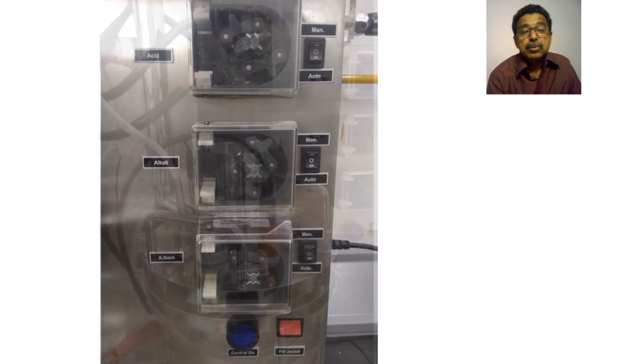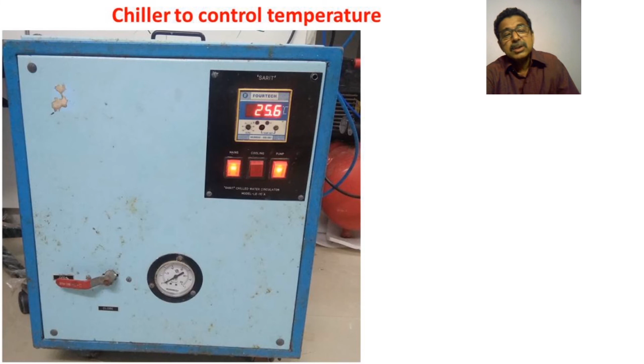This is connected with a chiller, which is also PID controlled. For example, if my run temperature is 25 degrees, I circulate 25-degree water to this — 25.6 is the temperature displayed. It constantly circulates this 25-degree water in the jacket, and that is how the temperature of the unit is controlled.